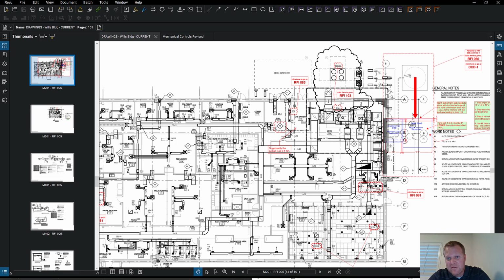The mechanical contractor said, hey, we've got the startup guy coming next week. So in the project manager's head, he's thinking, great, finally we can get that chiller going. But there was no piping completed between the chiller and the cooling tower, or the cooling heat exchanger over to the air handler. None of that was flushed, tested, filled, or conditioned, and the air handler wasn't running. So what's the point of starting one component? It's a great step, but it's the wrong question.